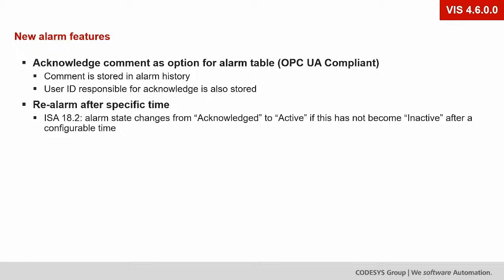The next feature is called realarm, and it is described in the ISA 18.2 specification. You can specify a time after which an alarm changes back to the active state if it has been acknowledged but has not yet been resolved after this time.